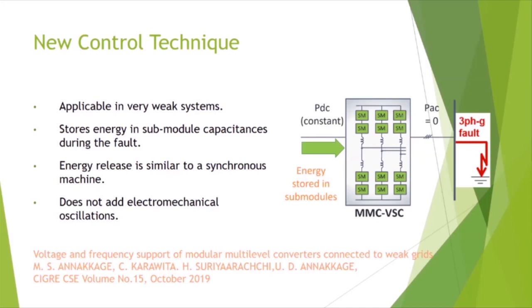To give you a very quick idea of how we do that, if you have 100 capacitors connected in series to get a certain voltage, now if you suddenly decrease it to 50, each capacitor will be charged to double the value. The stored energy in the capacitor is proportional to the square of the voltage. So you can see by reducing the number of submodules while maintaining the same DC voltage, you can increase the energy storage in submodule capacitors.